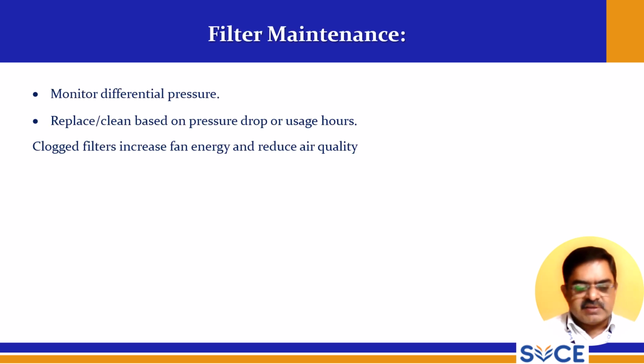Filter maintenance is also very important. It is similar to how filters are used and maintained in our automobiles. Filters play a major role: they clean the fuel and air supplied to the engine. In a similar way, we have to maintain filters in air conditioning and HVAC systems. For filter maintenance, monitor differential pressure, and replace or clean based on pressure drop or usage hours. Clogged filters increase fan energy and reduce air quality, and they also reduce the efficiency of the entire system. So clogged filters should be replaced at regular intervals. That is very important in maintaining filters.